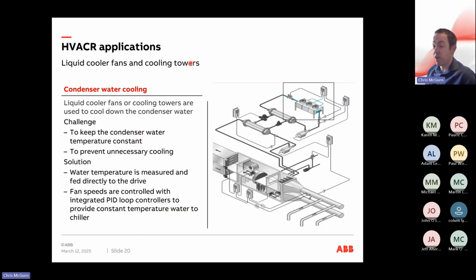So here's an example of a liquid cooler fan. What does it need to do? It needs to keep the condenser water and temperature constant. It needs to prevent unnecessary cooling. How does it do it? The water temperature can be measured and fed directly into the drive. You can do that directly without using a PLC if you know how to set it up. And then the fans can be controlled with integrated PID loop controllers to provide a constant temperature. So that gives constant feedback to the drive to tell it to speed up or slow down as necessary. And that ensures that you're not running at full speed all the time, cooling water when it's unnecessary.